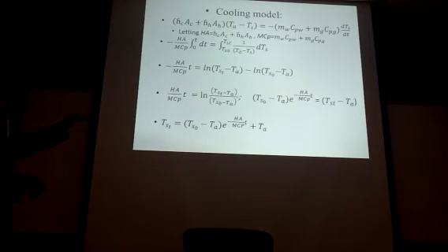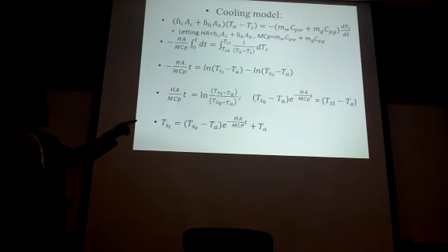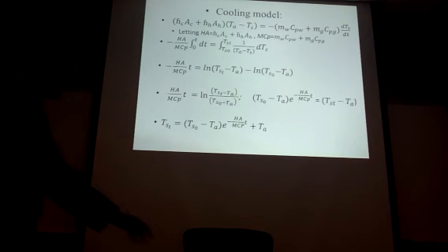So after doing this, I know the surface temperature, I know the ambient temperature, I know all those other values. The only thing that needs to be known is the HA. And HA is the sum of the heat transfer coefficient of the cylindrical part times its area plus that for the hemispherical part. The reason for doing this is that the heat transfer coefficients for the cylindrical part and the hemispherical part are not equal to each other, so we cannot just add them. But we can take the product of the area and the heat transfer coefficient, and then operate with them.